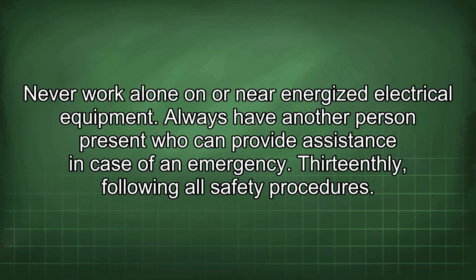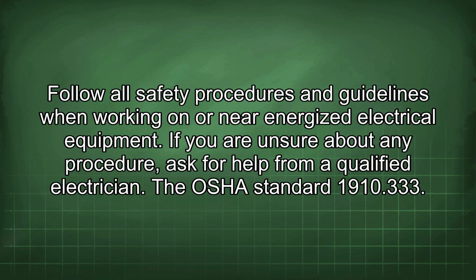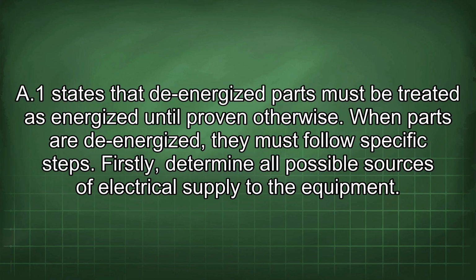Thirteenthly, following all safety procedures. Follow all safety procedures and guidelines when working on or near energized electrical equipment. If you are unsure about any procedure, ask for help from a qualified electrician. The OSHA Standard 1910.333(a)(1) states that de-energized parts must be treated as energized until proven otherwise. When parts are de-energized, specific steps must be followed.